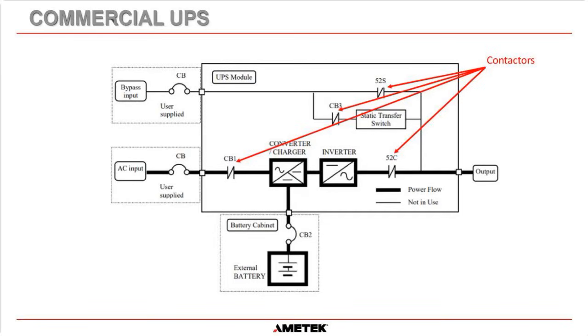Now, if you have any knowledge of plant operations, you will know that contactors, although they're fantastic, aren't the most reliable of things because they're mechanical. They have electromechanical coils, and they also move, and things can get stuck. Coils can burn out, and these can fail. So you can see this is in the critical path to the output of the system. And if that contactor fails in the open position, gets stuck open, then you cannot supply power from the inverter to the load circuits. So in my opinion, it's not great having a contactor as the output on the critical path of the inverter to the load. That's my opinion.